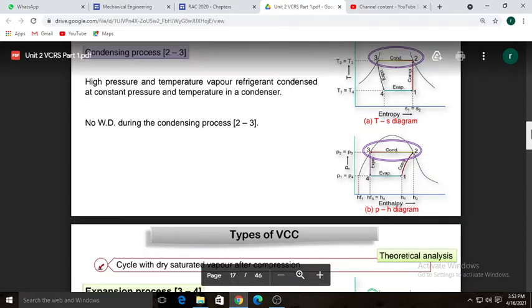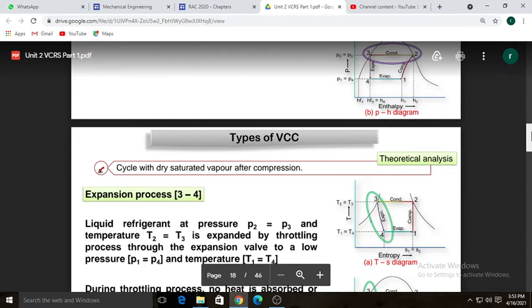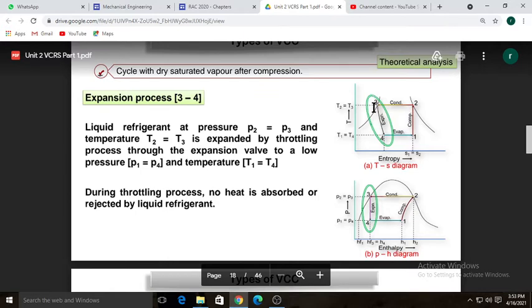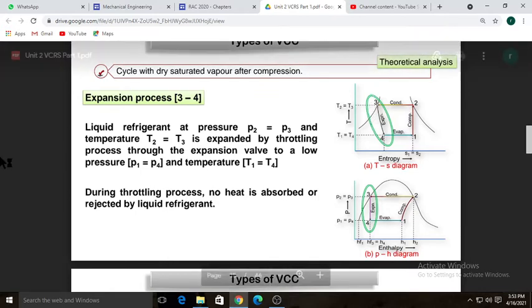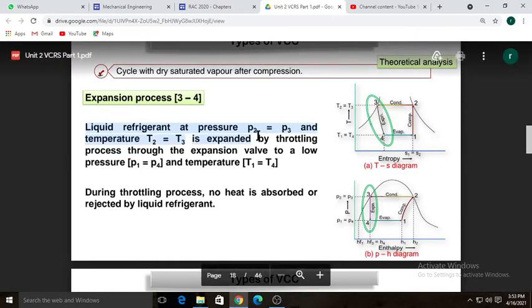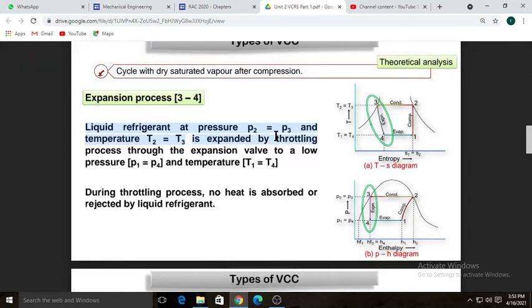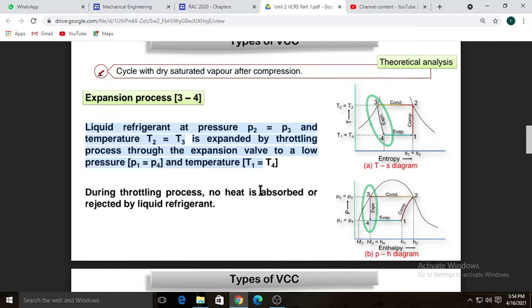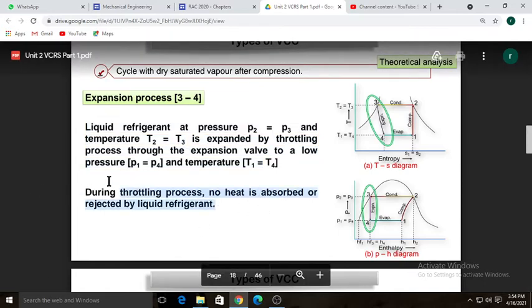If sub-cooling occurs, there will be a further temperature drop. Process three-to-four is expansion, where liquid refrigerant at pressure P2 equals P3 and temperature T2 equals T3 is expanded by throttling through the expansion valve to low pressure P1 equals P4 and temperature T1 equals T4. During the throttling process, no heat is absorbed or rejected by the liquid refrigerant.